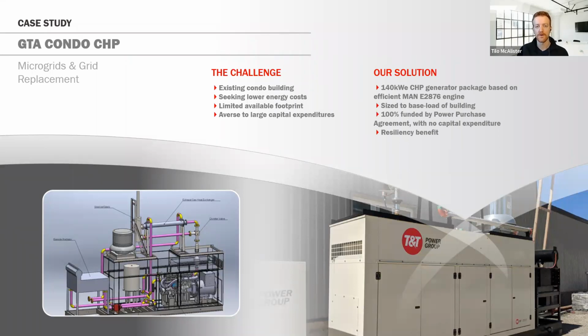If there's a power outage, a standby generator has to turn on, and it should be coming on routinely for regular checks and maintenance, but when you need something to turn on in a moment, there's always a chance it won't. A CHP generator is already running 24/7, so in the event of a power failure, it can be islanded from the grid. There are different configurations for doing that, but it's business as usual for the CHP, and it can energize your emergency loads or whatever you want to put on it. From a resiliency standpoint, that's huge, and that's why we see CHPs at hospitals, community centers, and different disaster relief designated areas.